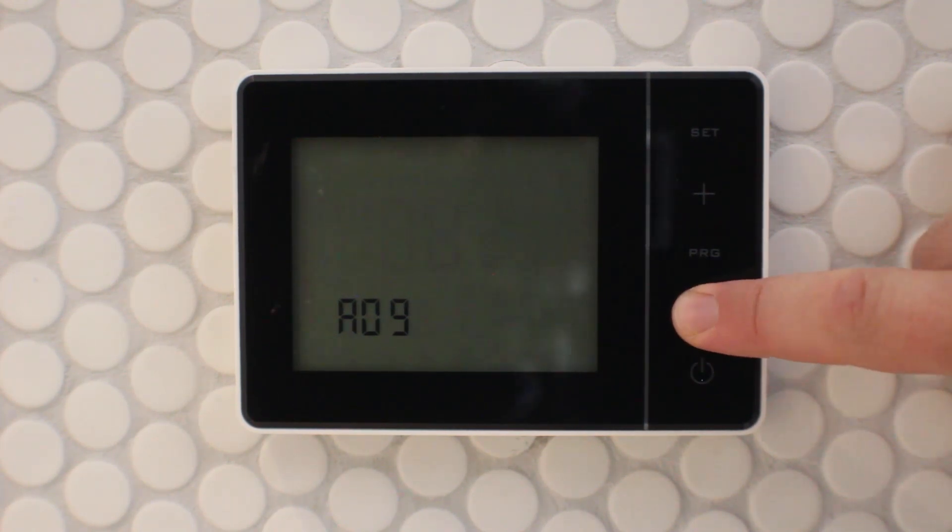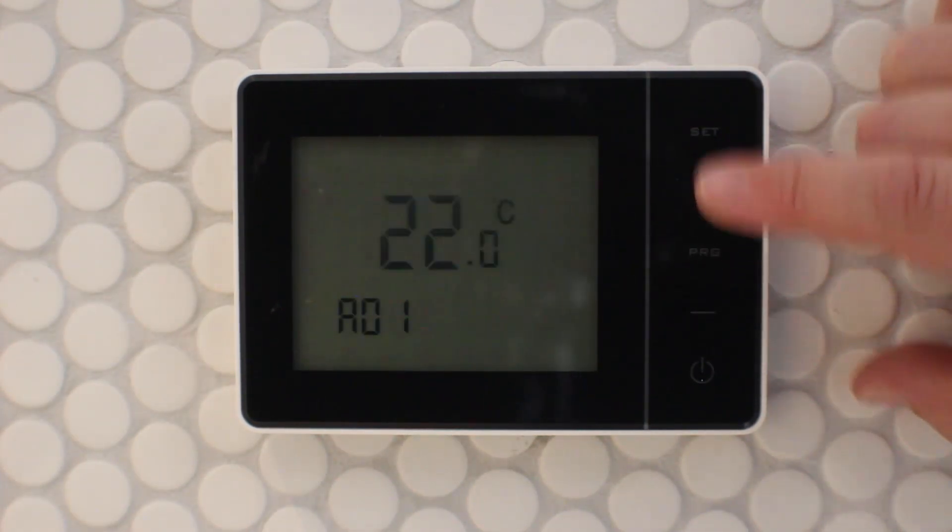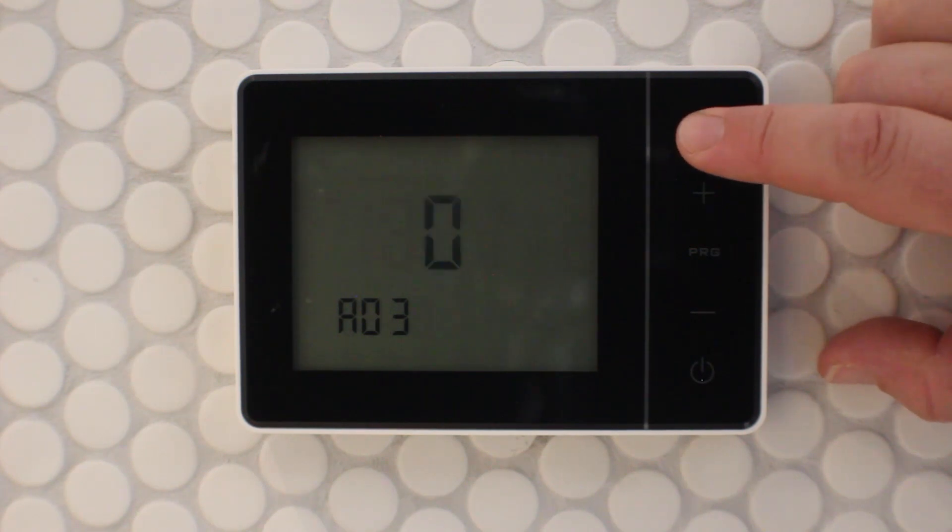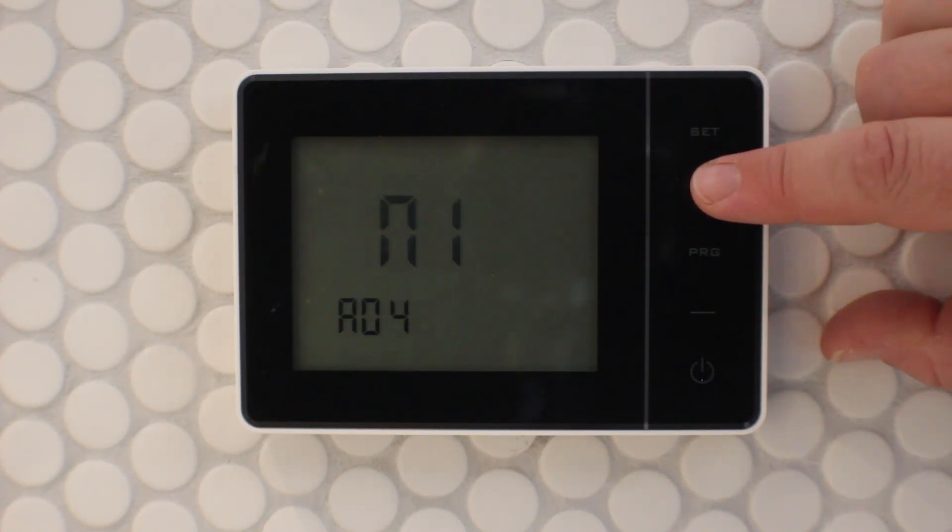If you experience an error number two, hold down the plus and set buttons. By pressing set, go to A04 and change it to NTC and set.